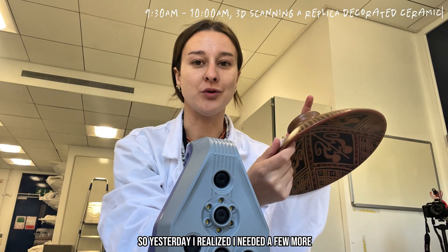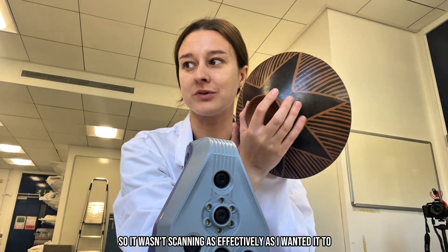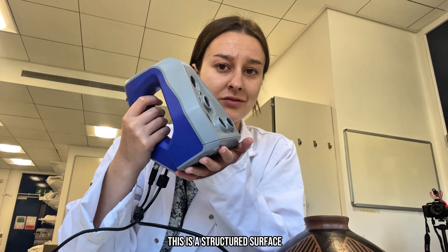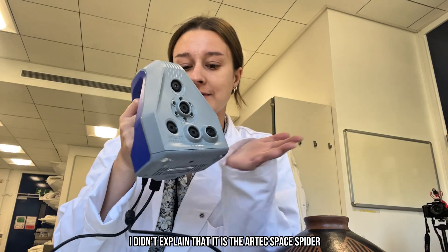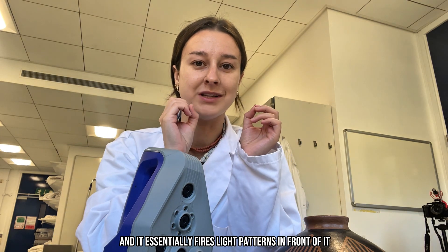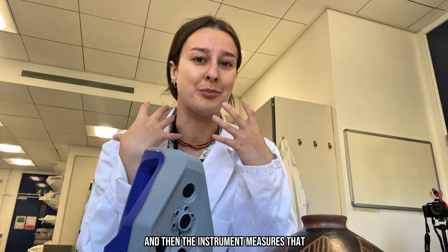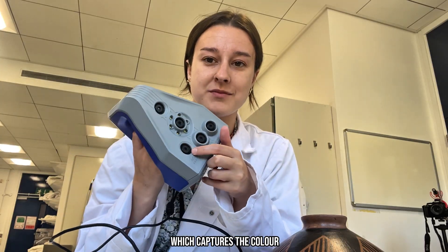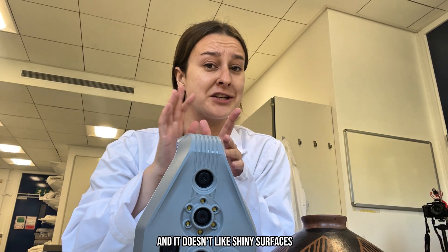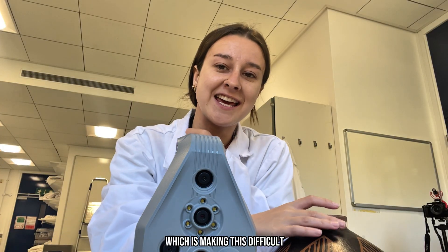Yesterday I realised I needed a few more scans to cover the whole of this because it is quite shiny, so it wasn't scanning as effectively as I wanted. This is a structured surface light scanner — the Artec Space Spider. It essentially fires light patterns at the object; they distort around the object and then the instrument measures that. There's a camera in here as well which captures the colour. It doesn't like dark surfaces and it doesn't like shiny surfaces, because the light just bounces back, which is making this difficult.